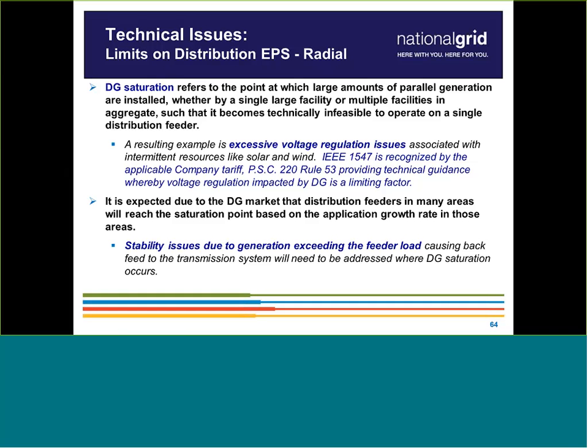and that's sort of what I would call feeder saturation, because we've talked about internally, okay, let's put a number on this. And we pretty much realized, from what I've seen, we can't put a number on this because it depends on the feeder. And so, in my experience, we have never told a customer, your DG on this feeder is not feasible. We'll tell you it's feasible, but it's this expensive. So it really depends a lot on where you are.